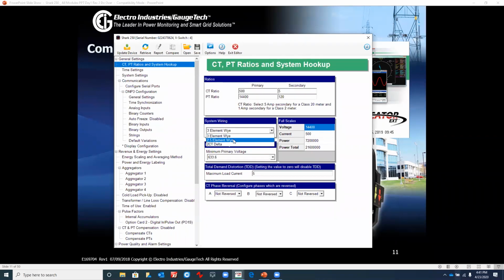You would choose a 2.5 element configuration, what we call a 2.5 element Y, where the connections are made with 2 PTs connected line to neutral. Although it's very rare, we do find that there are some existing out in the field where you will have to make that choice, a 2.5 element, and it's a huge difference from a 2 element. Some people think you could use a delta connection for a 2.5 element Y, and that would not work out because primarily the phasing and relationship between the voltage and the current vectors would be different in a delta connection.